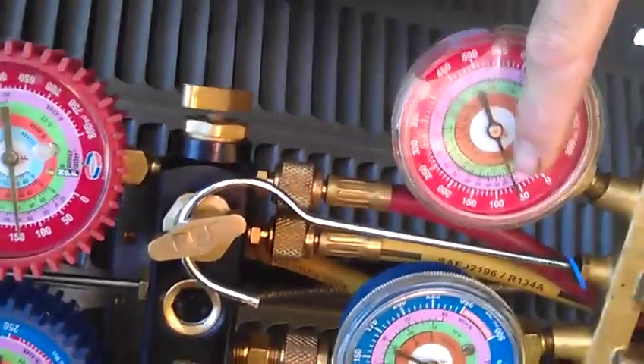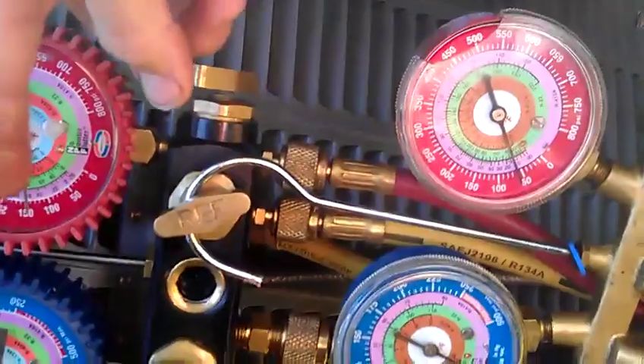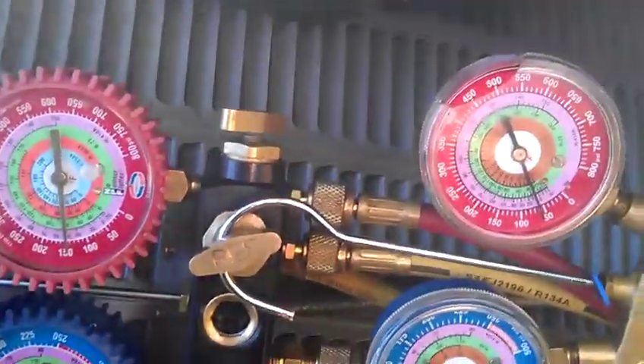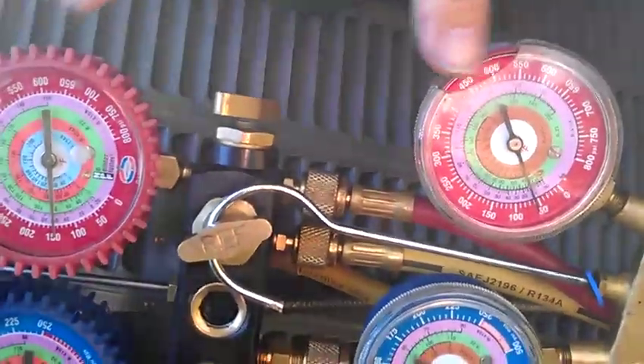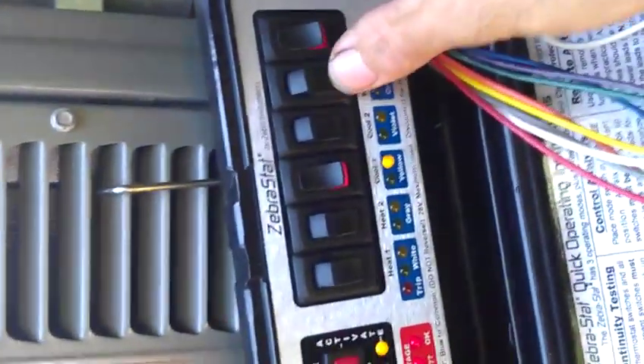Like I said before, I had a bad check valve on the inside and the one hooked to my liquid line dropped into a vacuum and my liquid line started icing up, but this one stayed about right. Now I've got the problem corrected. I just want to show this to you. So I'm going to come over here back to my thermostat and deactivate the reversing valve.